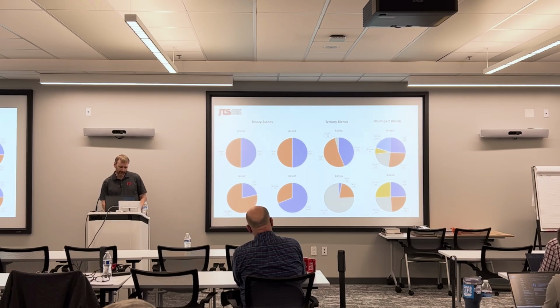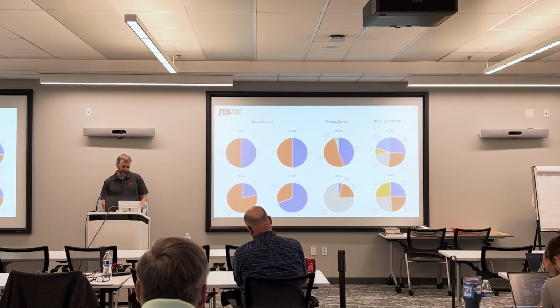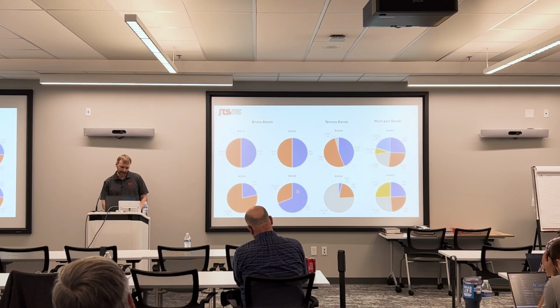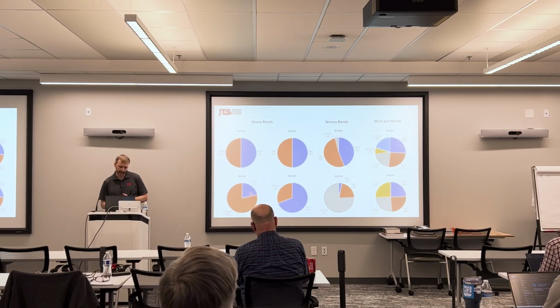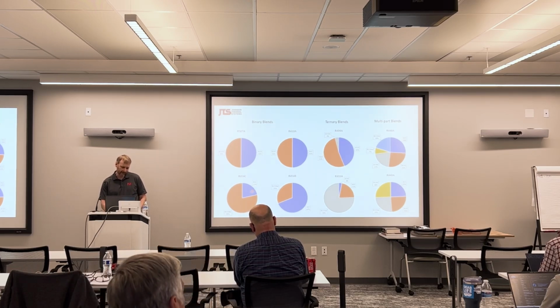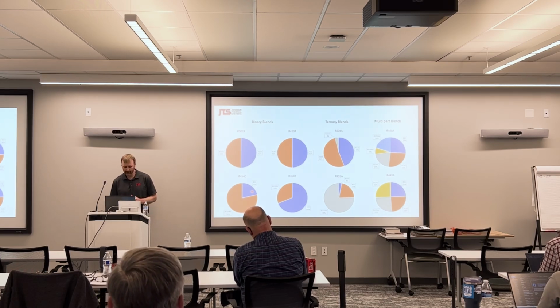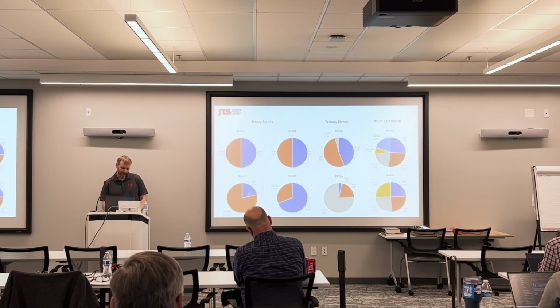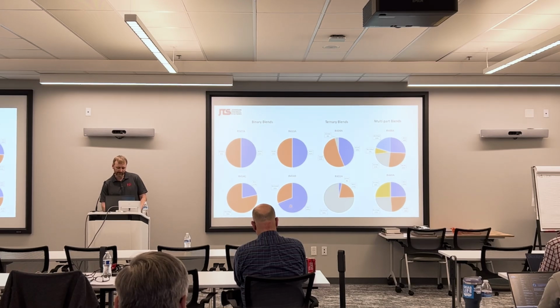Some of the newer refrigerants that are coming out include R454C and R454B. These both consist of 2 parts of A2L refrigerants. Both of them consist of R32 and R1234YF. However, they exist in different component concentrations. For instance, R454C has about 21% R32, whereas R454B has about 69% R32. All 4 of these are 2-part blends. They're known as binary blends.